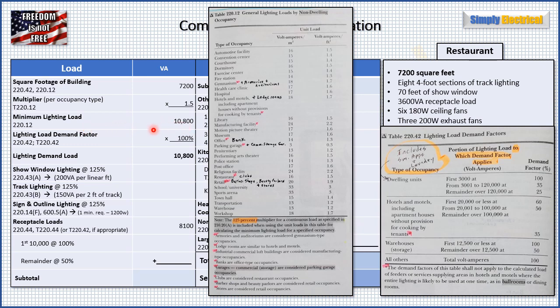Next, we figure out if we have any demand factor to apply to this minimum lighting load. We go to Table 220.42 — lighting load demand factors. Going down the list, we see dwelling units, hotels, motels, apartment houses, and warehouses — none of those are us. So we fall under 'all others' because restaurant is not specifically called out, and that category tells us the demand factor is 100%. So we get no break on our minimum lighting load, and our lighting demand load remains 10,800 VA.